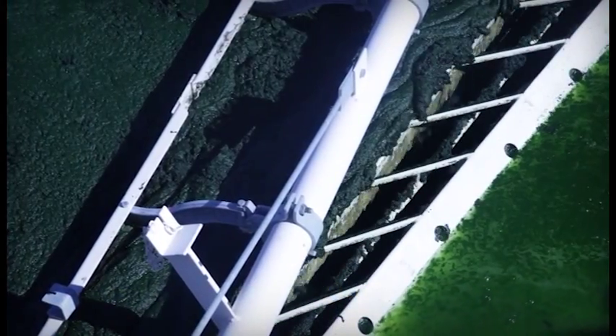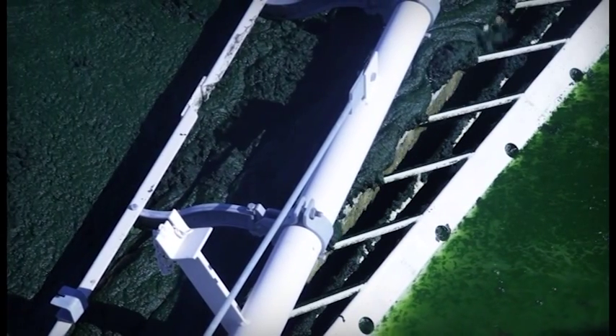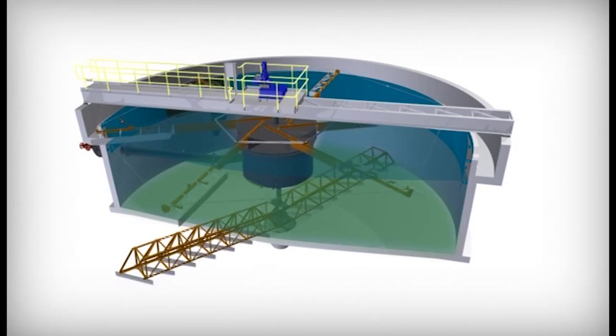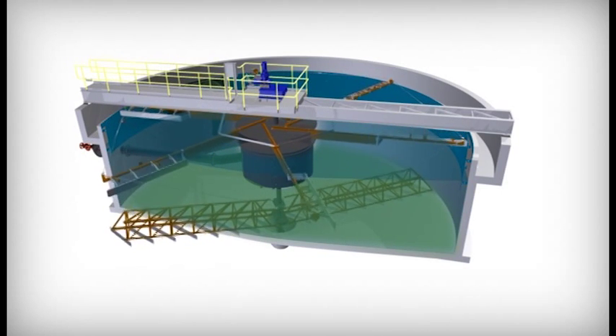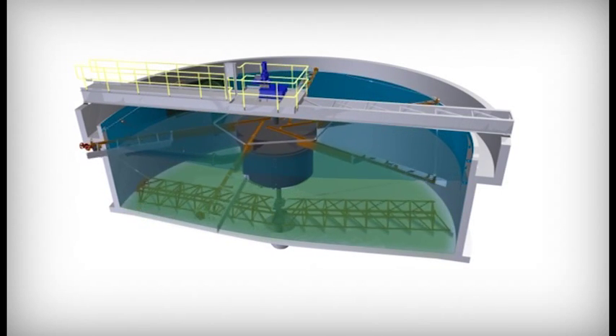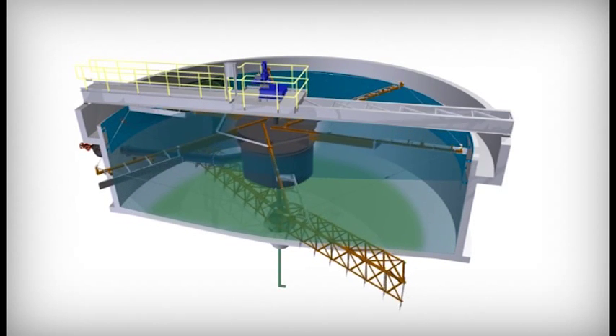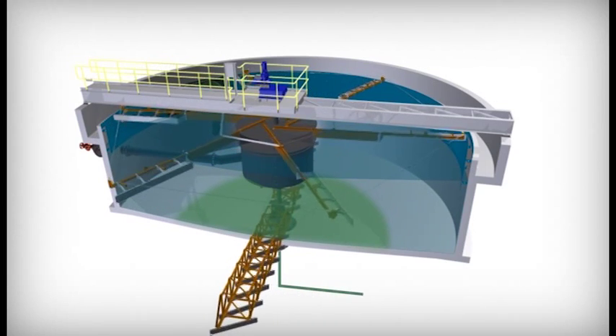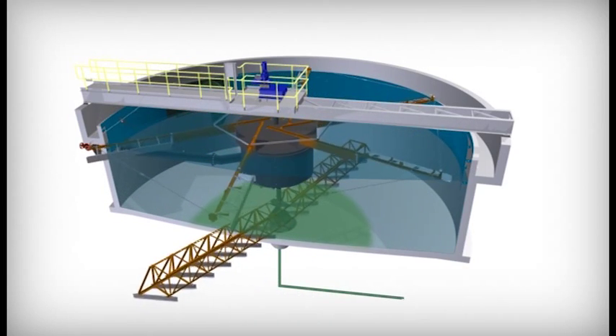Floating solids are skimmed into a float box by skimmer arms. Any settled solids are scraped along the tank bottom by sludge scrapers for removal from the DAF sludge hopper. Clarified effluent exits the tank under a float retention baffle and into an effluent chamber or launder.